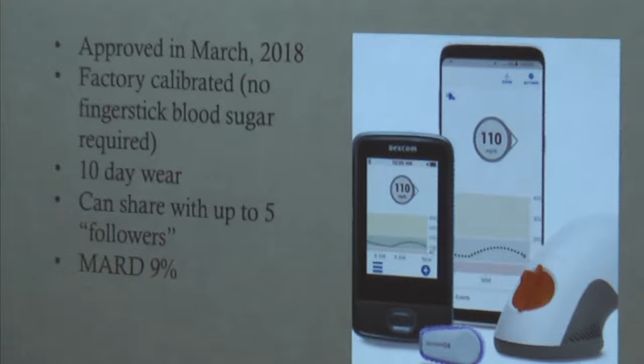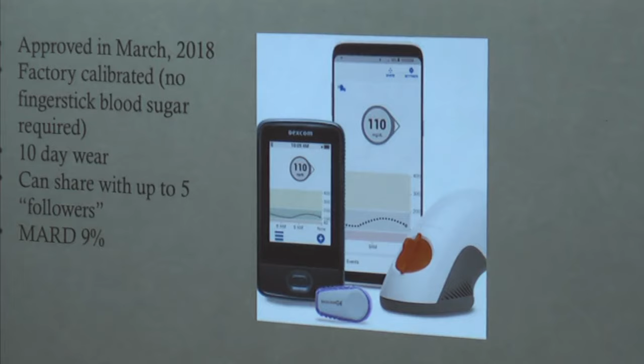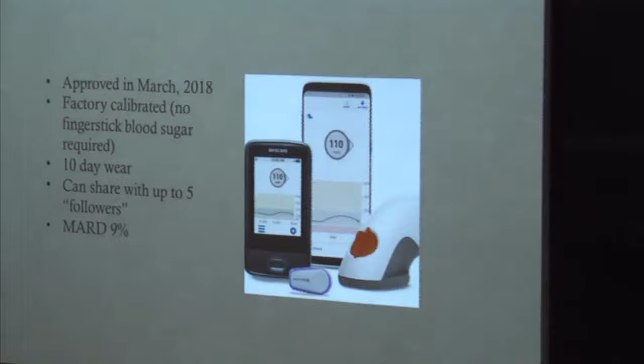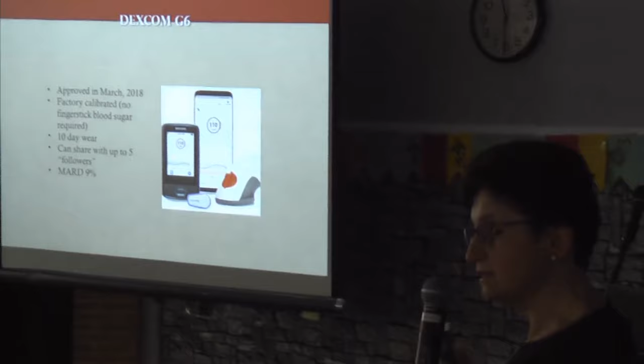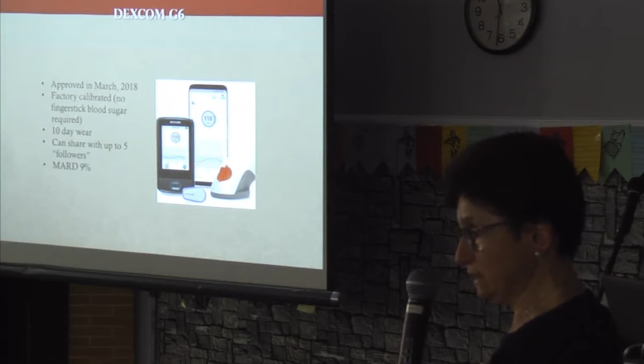So MARD stands for mean absolute relative difference. This is the measure that we all use for all meters, all sensors to see how accurate they are. What it reflects is the difference between the blood sugar measured by the sensor and the blood sugar measured by a reference device. Now, in the studies, the reference device was the lab glucose analyzer, which is way more accurate than the meters. When patients use just the meters in the real world, unfortunately, even sensors become less accurate because, as you see from the studies, the MARD for G6 was 9%. FDA approved accuracy for the meters is a MARD of 20%.